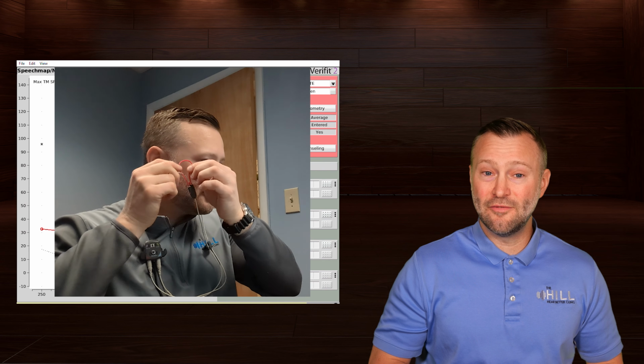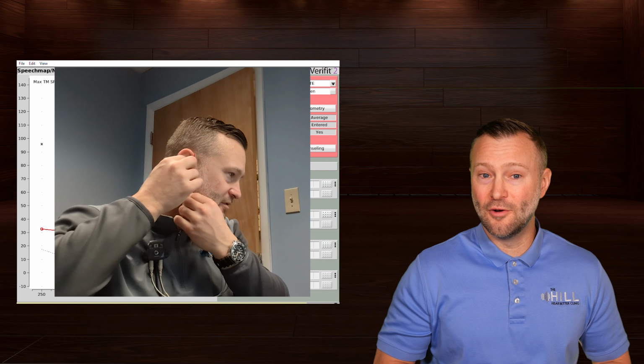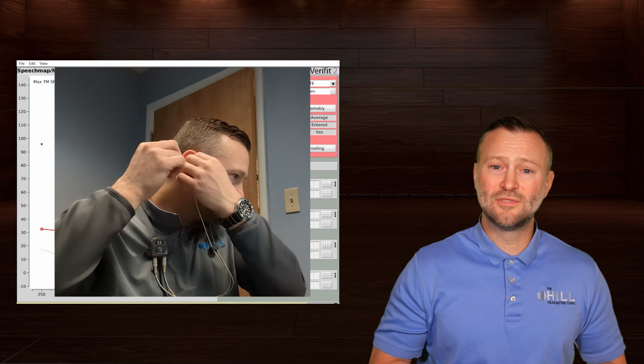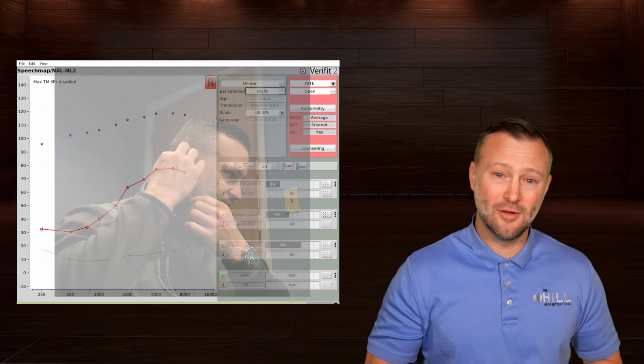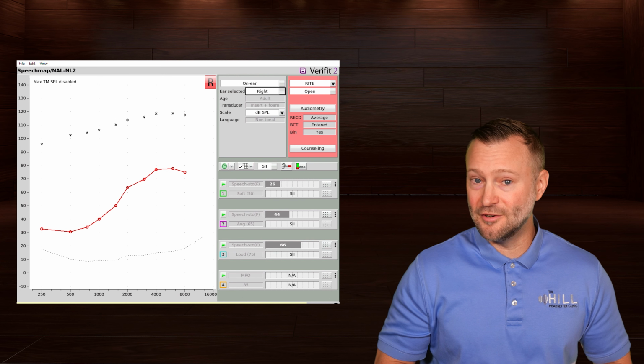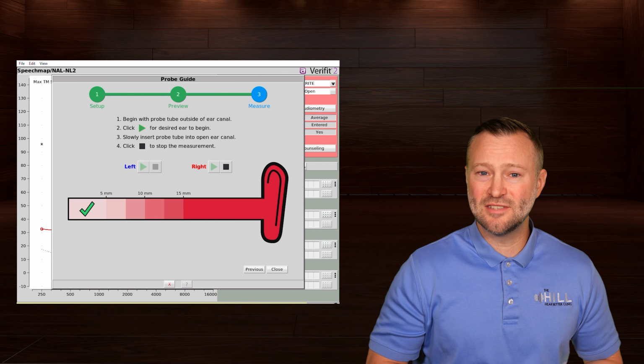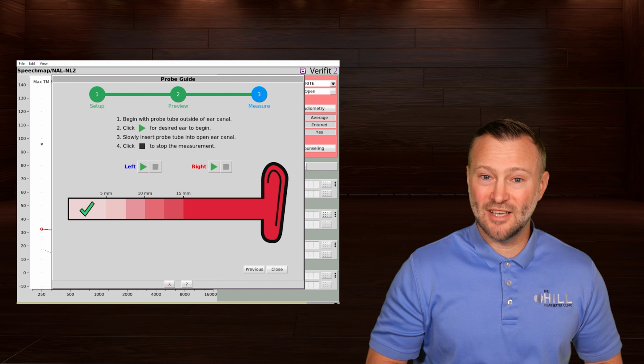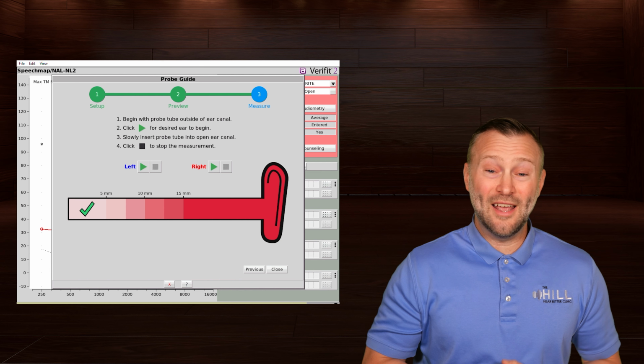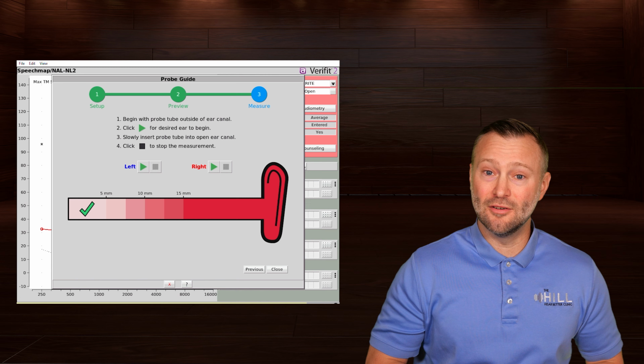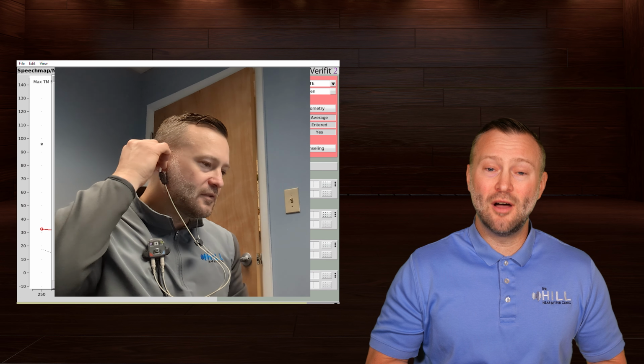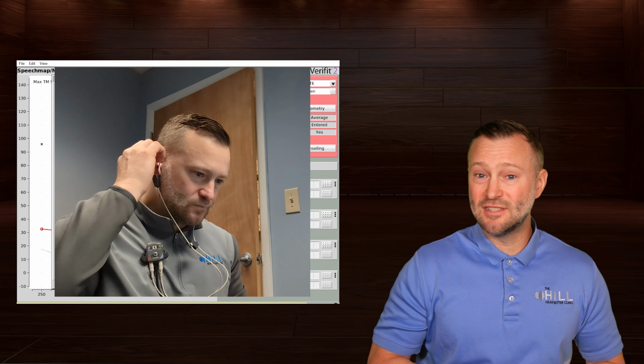In order to measure the devices, I first hang a reference microphone on my ear and then place a probe tube attached to the output microphone in my ear, 5 millimeters from my eardrum. I then verified the placement to make sure it was at the appropriate depth so the measurement would be accurate because I can't see in my own ear. Then I placed the Apple AirPod Pro 2 in my right ear to take the measurement.